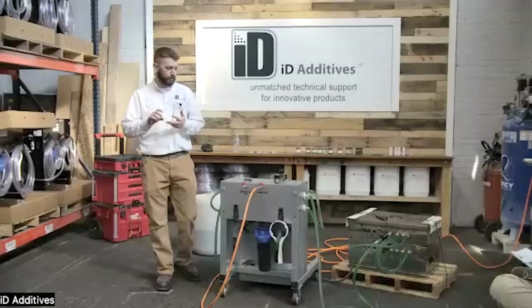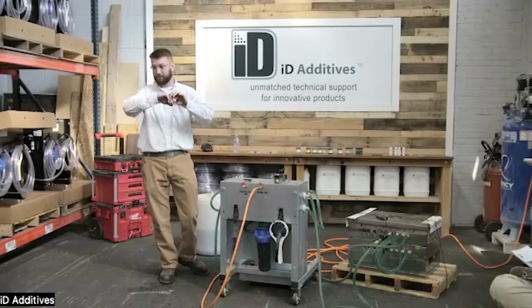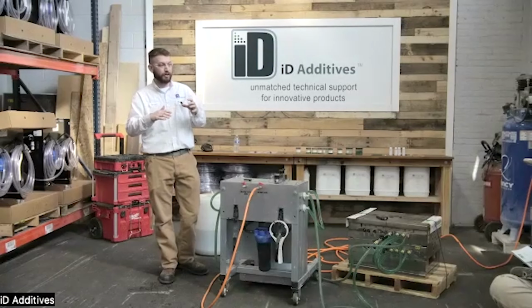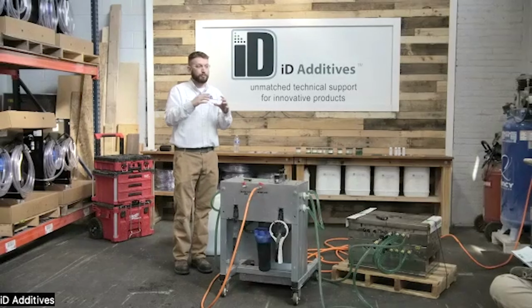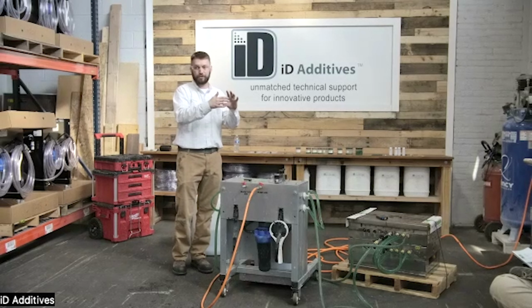Any type of buildup, as I mentioned earlier, can affect cooling by as much as 60%. It just acts as an insulating layer. So if I'm only getting laminar flow, I'm not capturing all of the heat transfer, and that's where turbulent flow comes in. It achieves two things: one, you're taking out as much heat as you can by capturing all of the surface area; two, with turbulent flow, you're not giving contaminants a chance to collect because you've got such good flow.